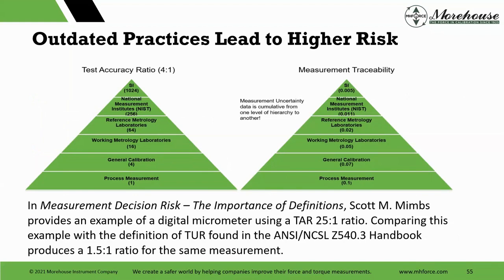And he provides an example in there of a digital micrometer, because I don't want to use everything with force. It gives a 25 to 1 TAR ratio, and then he compares that with the definition of TUR found in the ANSI Z540.3 handbook and produces a 1.5 to 1 ratio for the same measurement. We were seeing that earlier. And here's why it's not sustainable. Test accuracy ratio in a closed system could work. I don't want to get too far into it, but look at this.